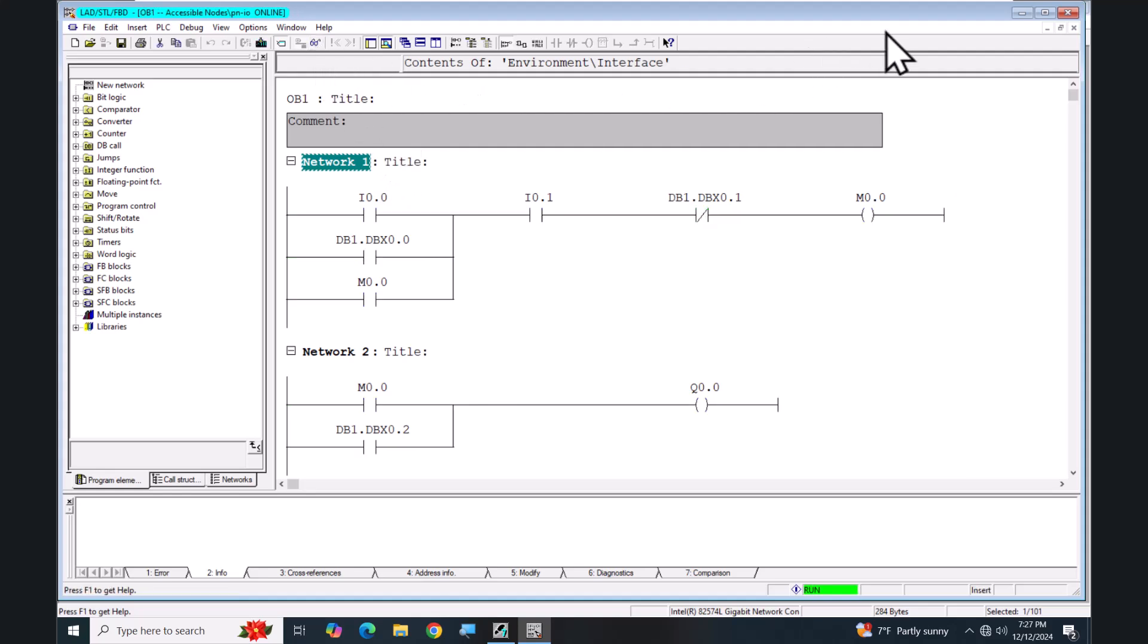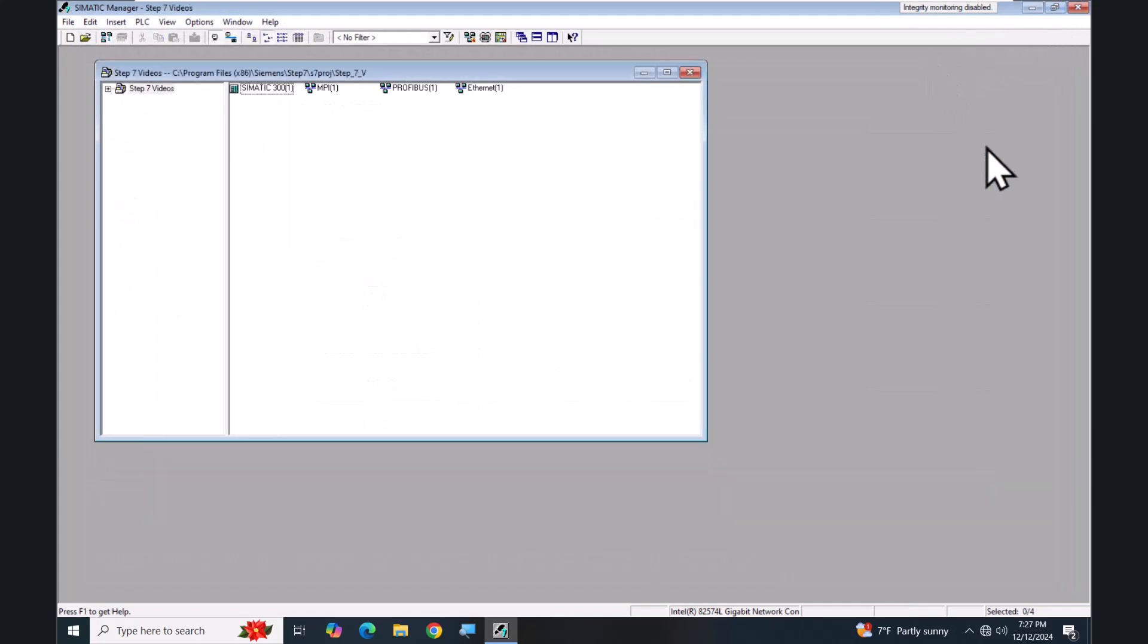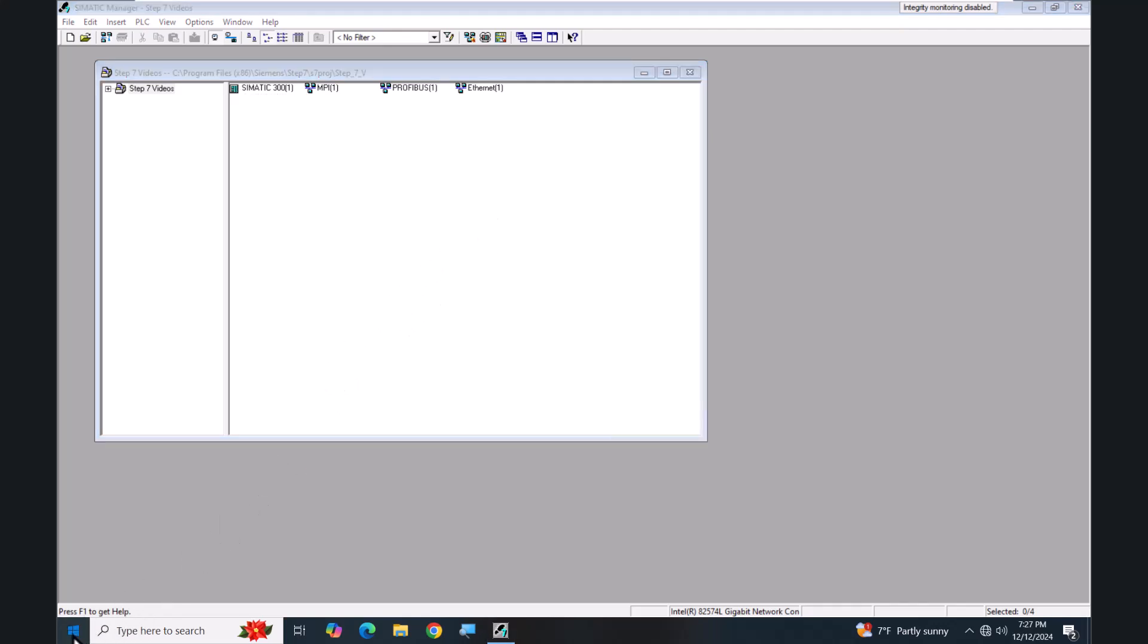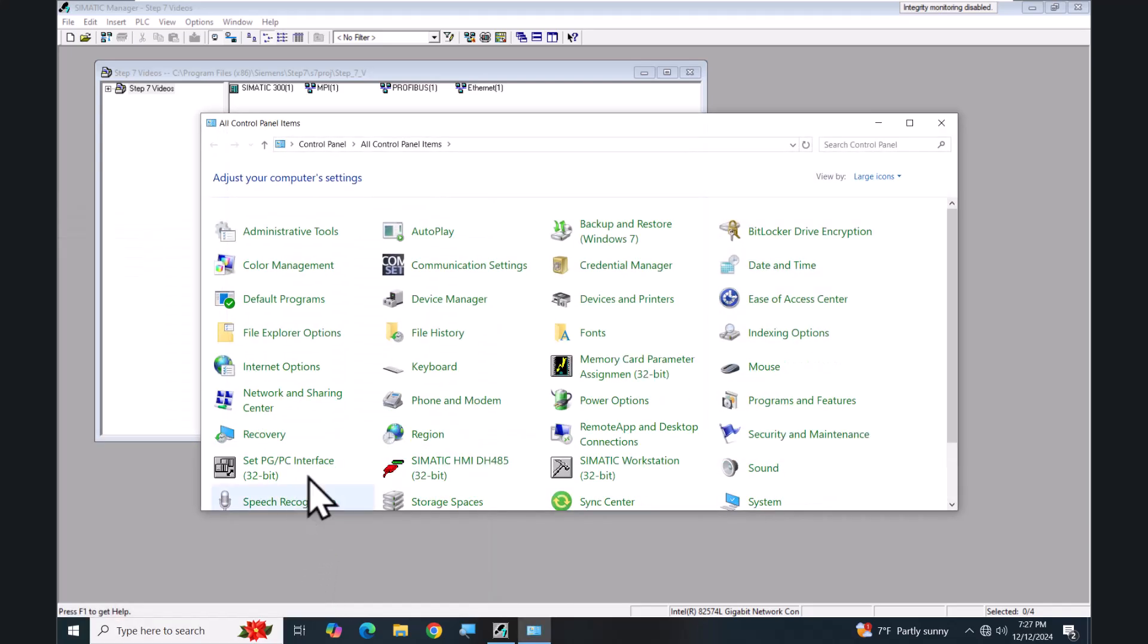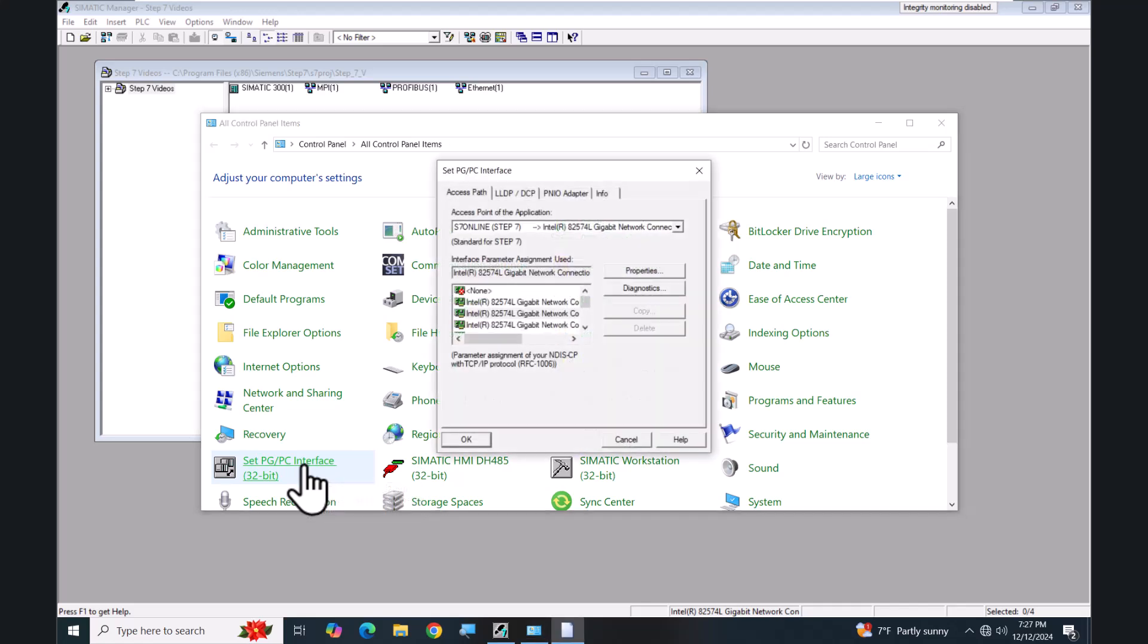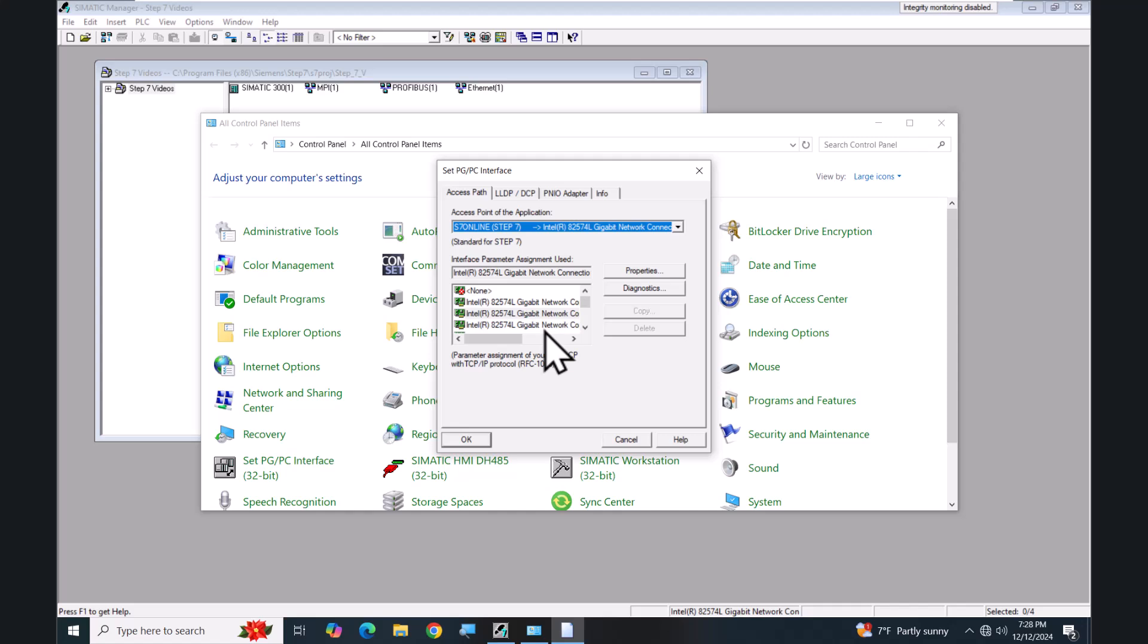I will stop monitoring and close out this window. Now we'll close my Accessible Nodes. You can also configure the Set PG/PC Interface through the Windows Control Panel. There's an icon for Set PG/PC Interface. When I open that up, the only difference is when you do it at the operating system level, the S7 Online is not automatically fixed for you. So in this case you can actually configure additional access points in the application, but Step 7 is always going to use the S7 Online. Then you would be able to pick whatever Ethernet interface or whatever interface that you would like to assign to the S7 Online logical access point of the application.